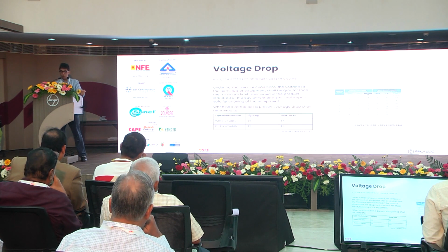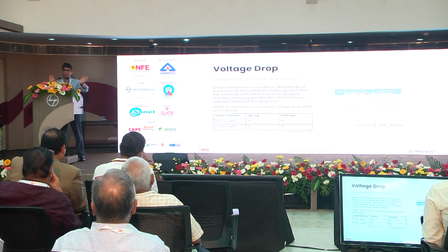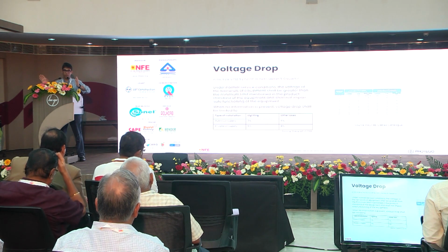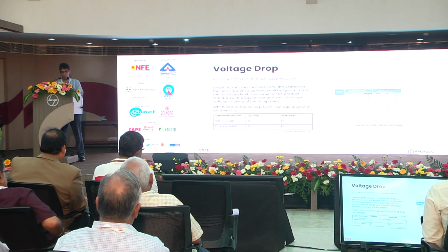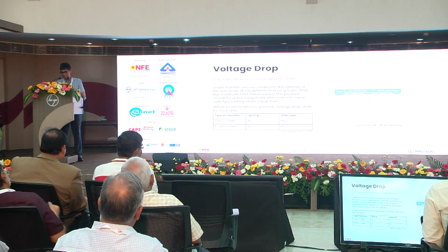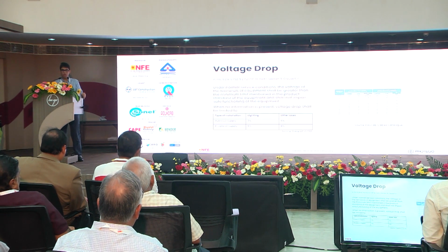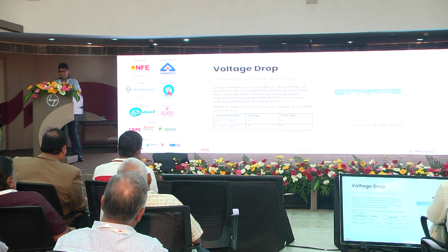And if this is not provided, usually equipment will say 200 to 240 volts, or 200 to 250 volts is their range. If that information is not provided, then there's a simple thing as per Table 47 of IS 732. If it's a public LV supply, you're allowed 3% for lighting, and if it's any other use like power, you're allowed 5%. If it is a private LV supply, 6%, 8%.